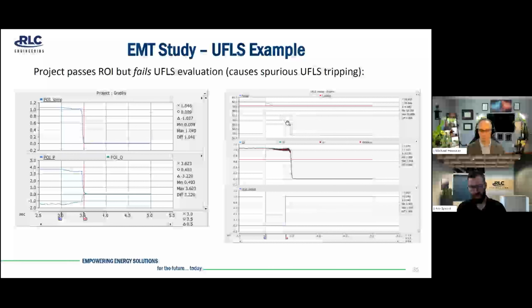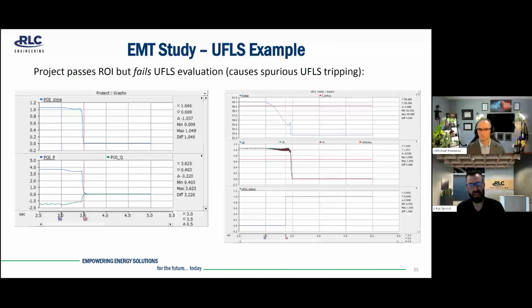However, there's one safeguard to this, which is namely voltage block settings, or sometimes referred to as voltage inhibit. So this second plot shows the 3 voltage traces for A, B, C voltages, as well as the voltage block setting here on this horizontal line. So essentially what happens is if your frequency goes below the frequency trip setting for a certain amount of time, your device will look at the voltages, and if they're above this voltage block setting, then your UFLs will activate. However, if they're below the setting, then it would effectively block, as the name would indicate, the UFLs from operating. And that's really a safeguard to ensure that you're not tripping on UFLs under normal fault events that could happen right local to your distribution system.